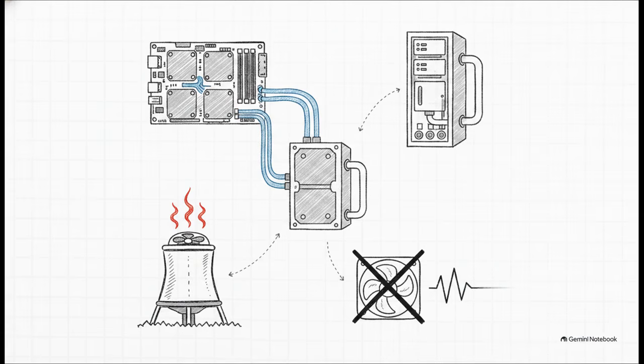First off, they're using cold plates that cover almost everything: CPUs, GPUs, PCI switches, DIMMs, power supplies. That captures up to a staggering 98% of the heat. To handle all that, Supermicro introduced new in-rack coolant distribution units, or CDUs, that remove 250 kilowatts of heat per rack. That's a 150% capacity increase.